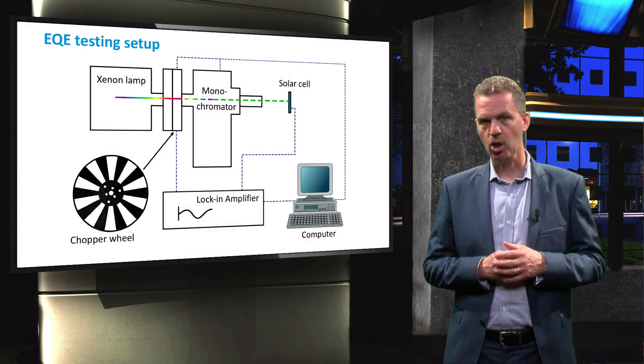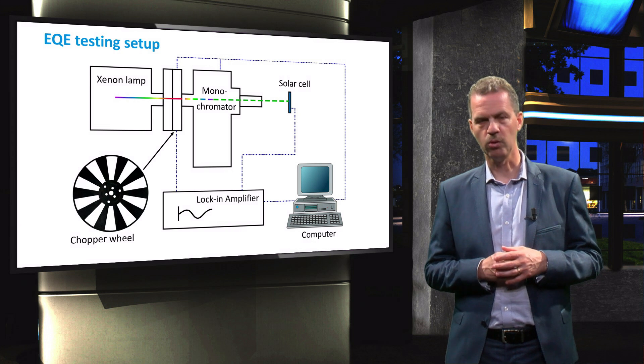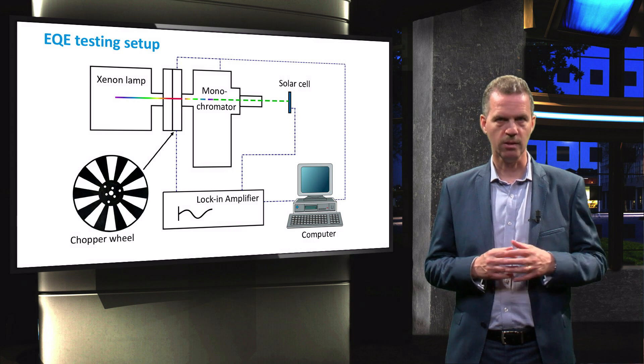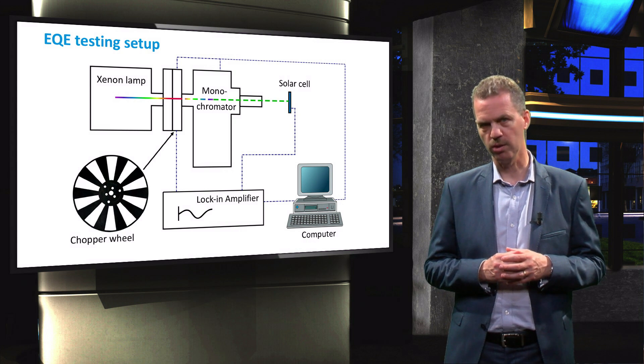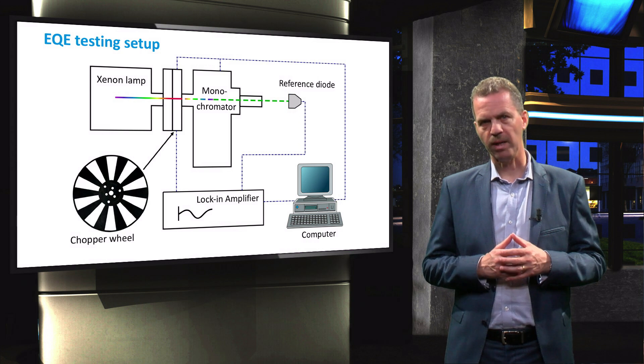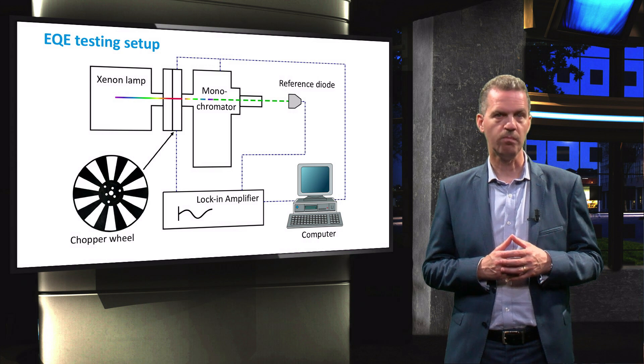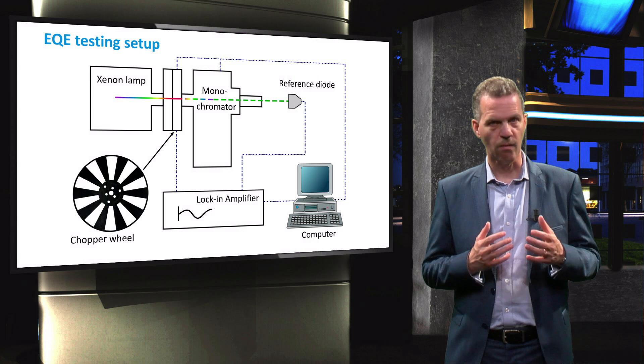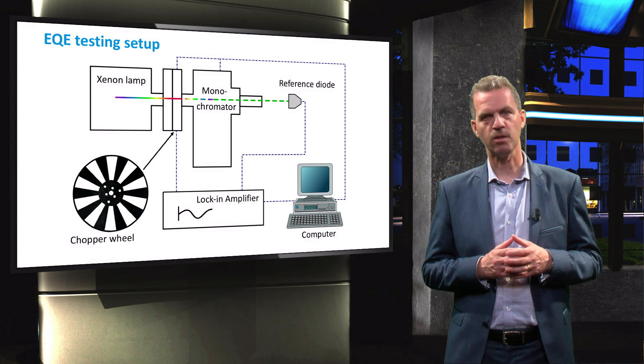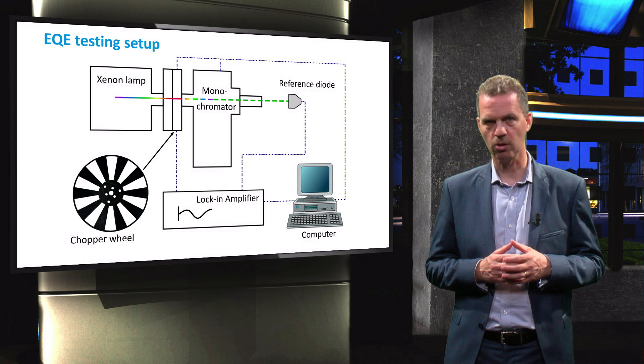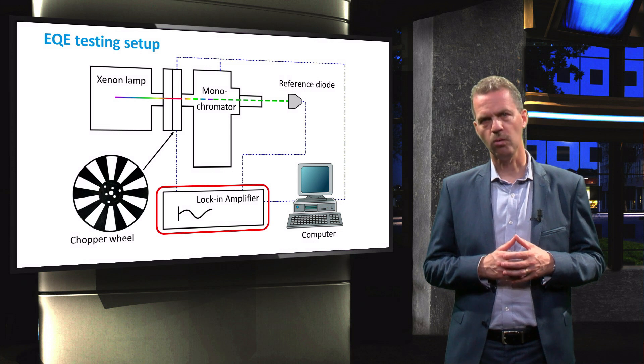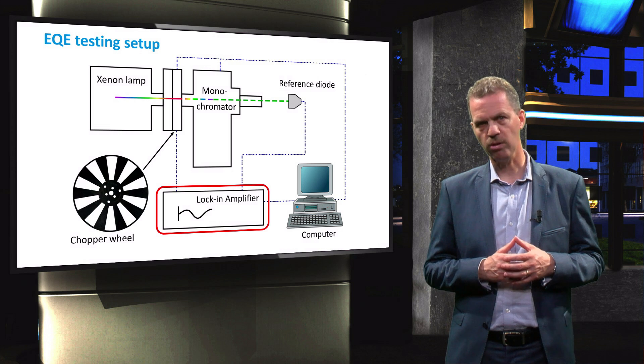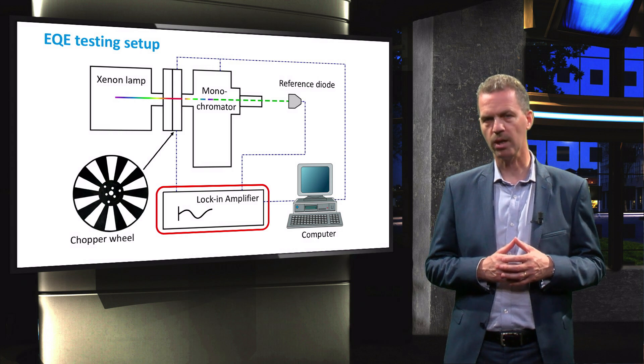The monochromator, chopper wheel, and lock-in amplifier are usually all controlled by a computer, which programs the setup to scan through the entire light spectrum and measure the response of the solar cell. Since the spectral photon flux of the lamp should be known very accurately, a reference diode with a calibrated spectral response is measured prior to measuring the solar cell under test. We will now go into a little bit more detail on the method to retrieve the signal with a lock-in amplifier.